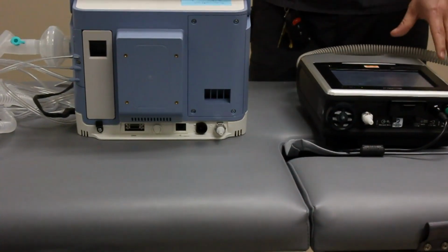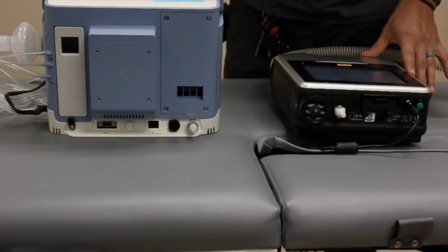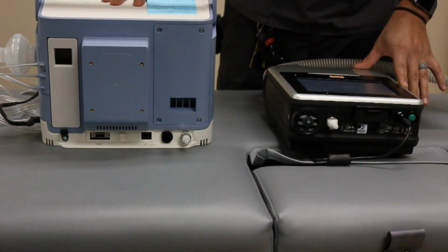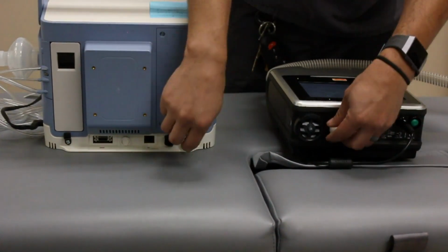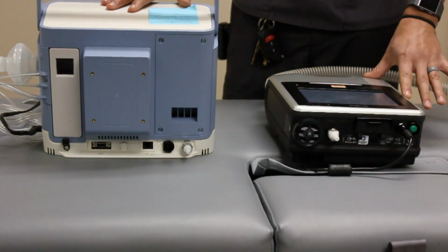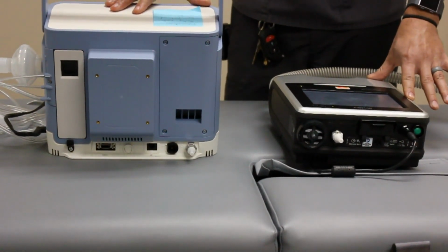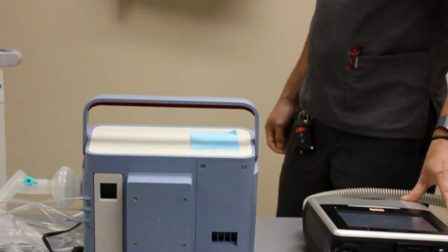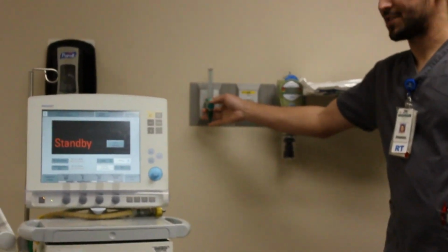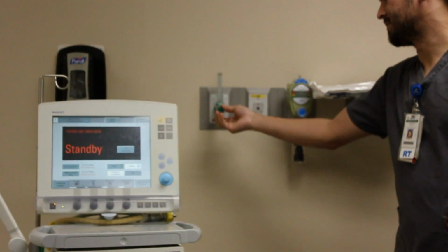On both of our home vents here, the Trilogy and the Astral, you connect oxygen tubing directly to the back of the vent through this nipple. On both vents, if you need to go up on the FiO2, it is as simple as taking the flow meter, which would have your oxygen tubing attached to the vent, and dialing up the flow.